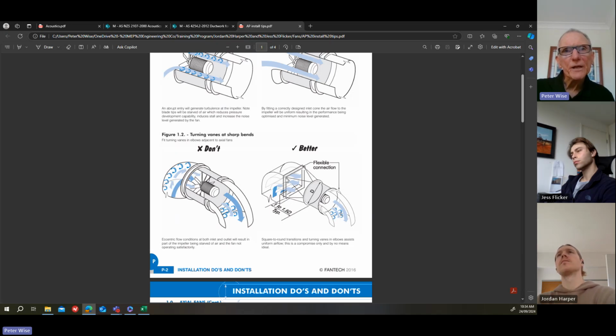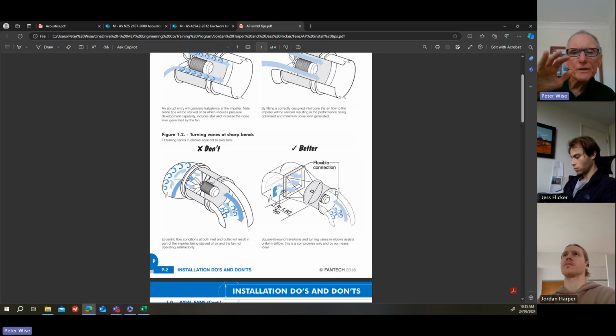The point I'm making here is the location of that flexible connection should be a duct length back, or the transition. If you're having a transition from a rectangular to a circular fan, put it upstream of the transition. On the discharge side of the fan, it's not a problem to put the flexible connection right at the fan, as they've indicated here, right on the discharge, because on the discharge side, there's a positive pressure, which is going to tend to force the flexible connection out. So you've still got a clear passageway for the air to go through. But if you have it at the inlet, it'll pull it in, and that's a problem.